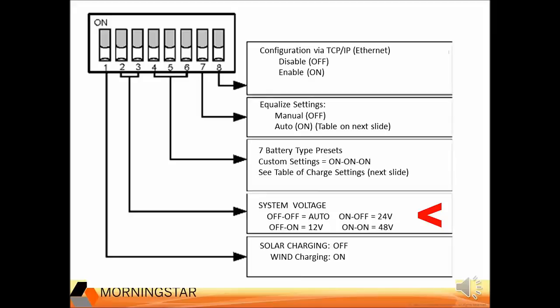This adjustment is also important when custom programming for other nominal voltages such as 36 volts. If you set it to 48 volts, a multiplier of 4, you would program it to 9 volts nominal — three-quarters of the 12-volt settings — since 4 times 9 equals 36 volts. If you set it to 24, a multiplier of 2, you would program it to 18 volts nominal.